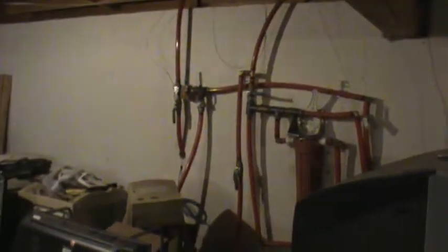This piping network over here is actually the piping that goes out to the tanks. Behind that concrete wall is where I buried two side-by-side 500-gallon propane tanks. At the time, I wasn't sure if I wanted the water to run through one tank and then to the other, or through both at the same time. Well, it turns out it's better to run through one and then through the other.